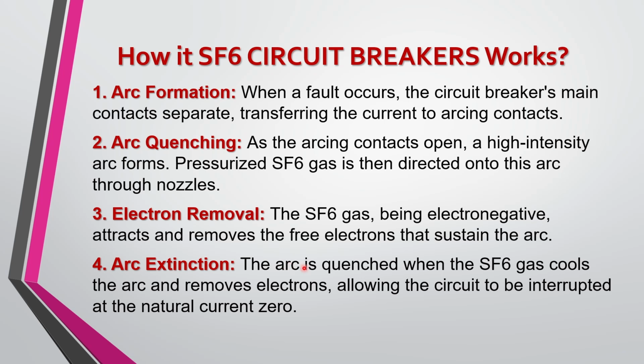Arc extinction. The arc is quenched when SF6 gas cools the arc and removes electrons, allowing the circuit to be interrupted at the natural current zero. So in the AC circuit, as you know, the current passes naturally through the zero level. So when it passes through this zero level naturally, the circuit breaker is disconnected or the interrupter is made to operate. So thus contacts are separated and the arc is quenched at the same time.